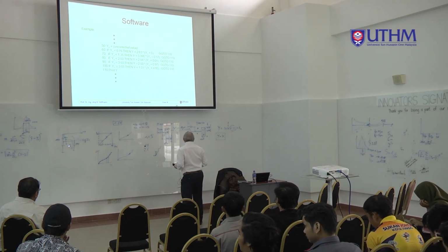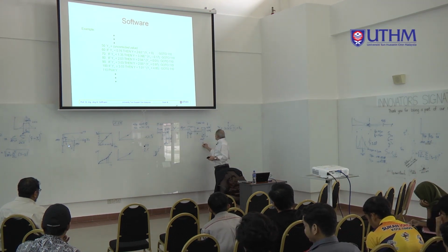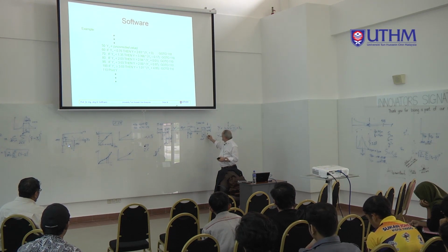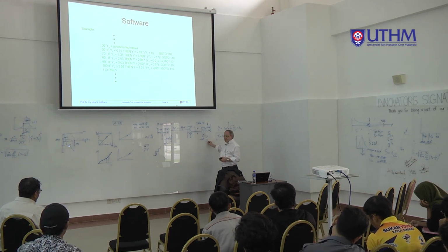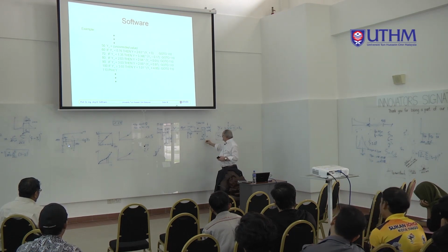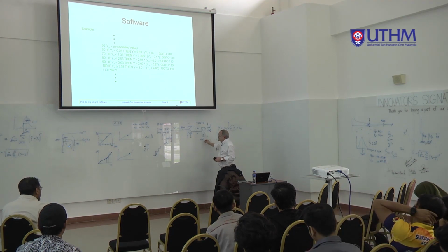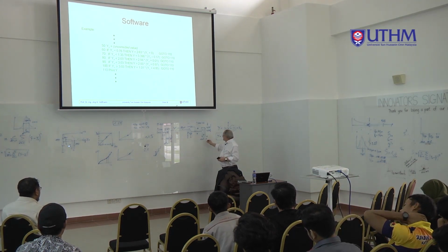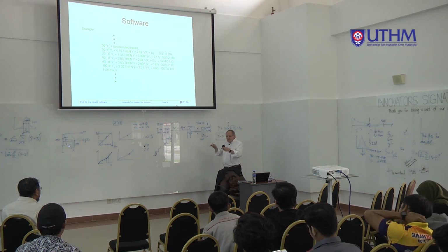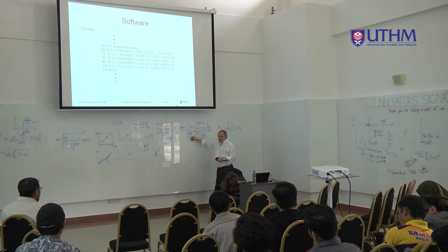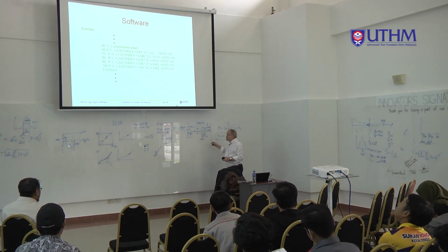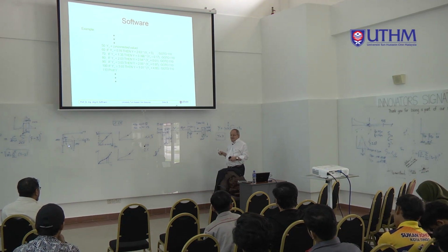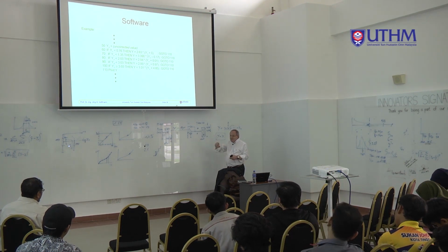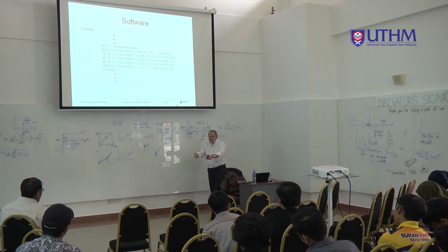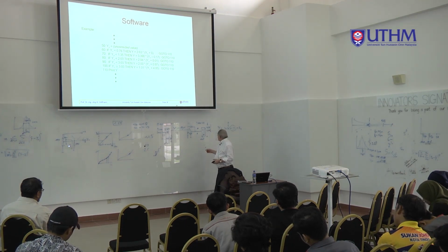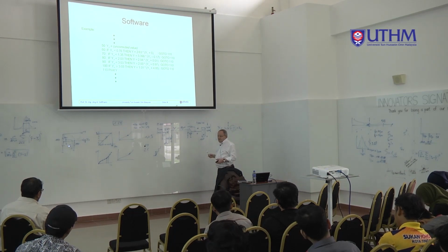That is also every time the problem. I explained it with the 12-bit, but when you use an ADC with a higher resolution, for example 16-bit, it's not only that you replace the ADC, also the disturbances from the sensor must be low. The noise from the amplifier must be so low that you can use this 16-bit. And if you have an analog sensor which produces spikes or has an influence from outside, then it makes no sense to use an ADC with a high resolution.